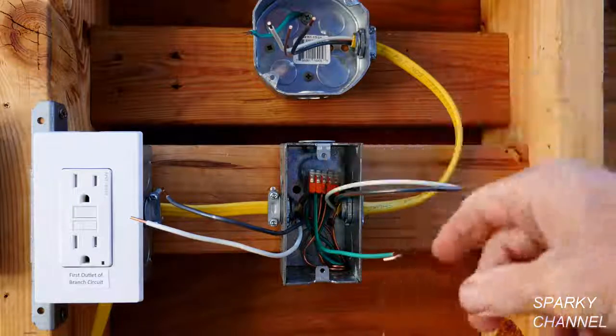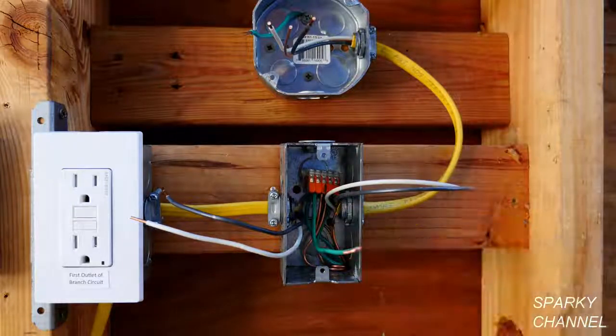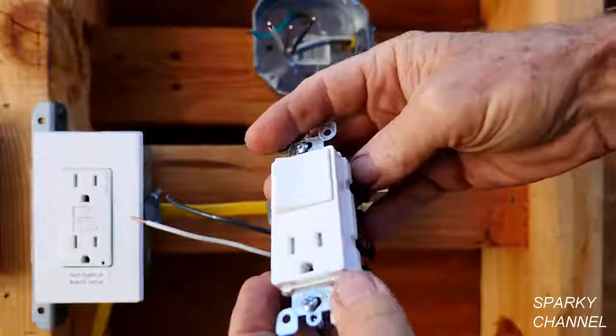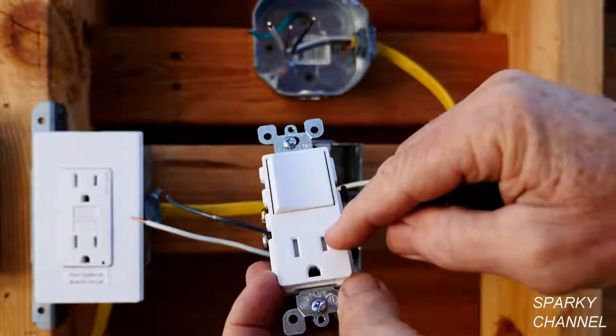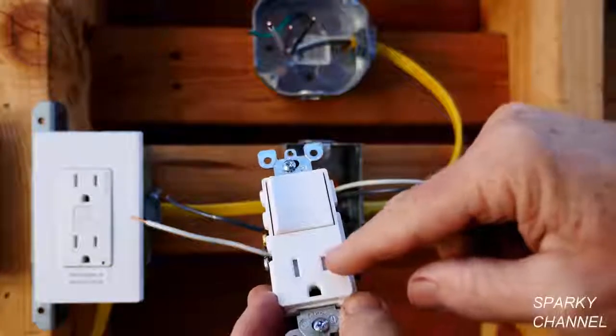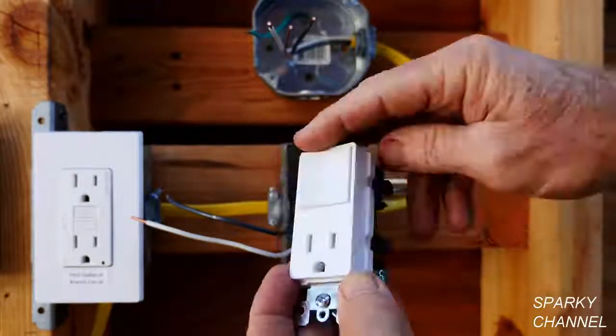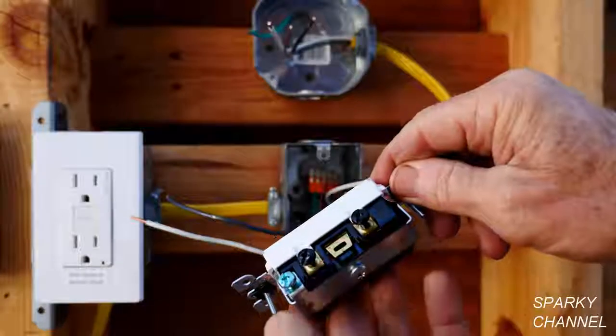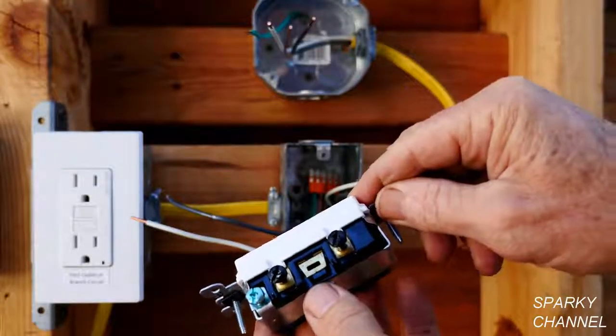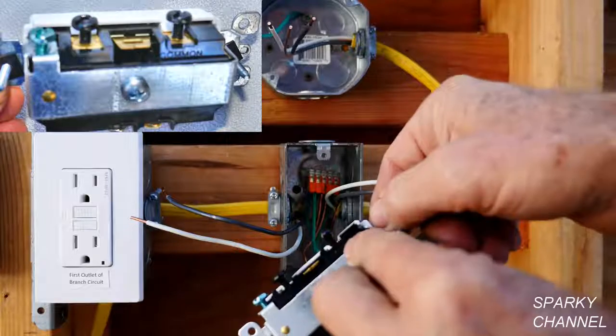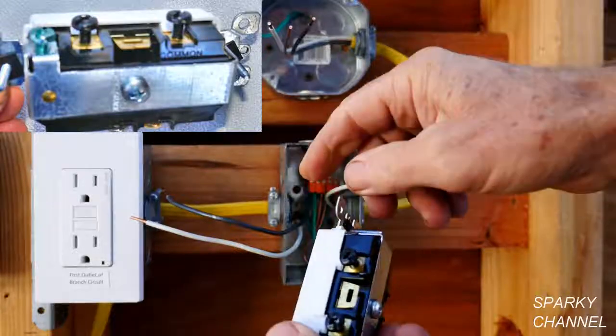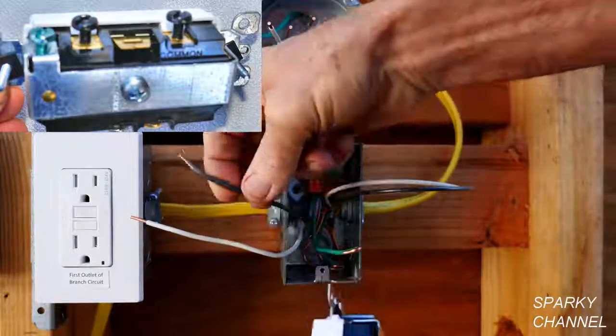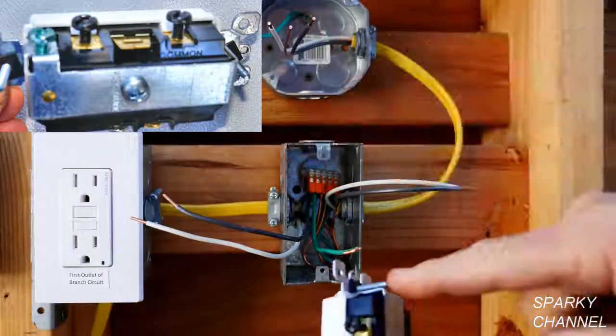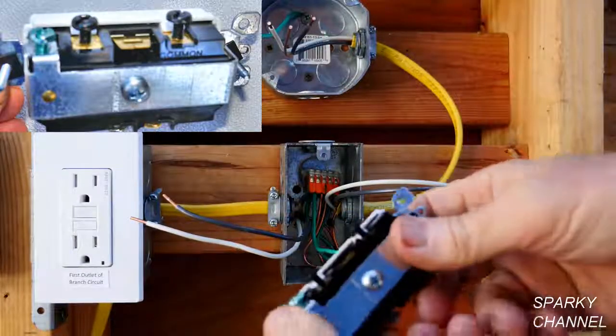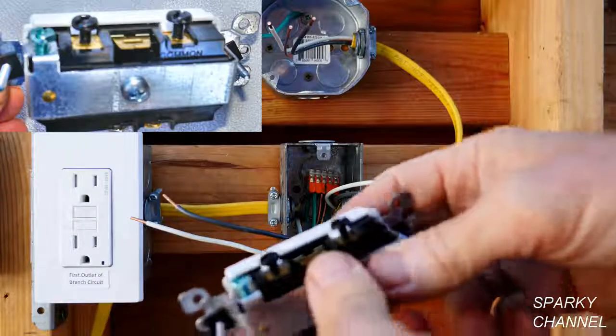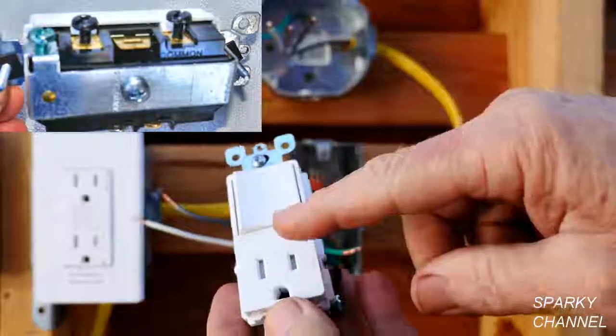Now push the grounds back into the back of the box, and we have a pigtail here ready for our device. You see, on the side with the short terminal, this is always your hot terminal. You turn it like this, and you have 2 black screws as well as the green grounding terminal. This screw is labeled common. So you put the line wire, we have determined that this is the line wire, you put the line wire to the common. That will take care of your electrical energy for both the switch and the receptacle.